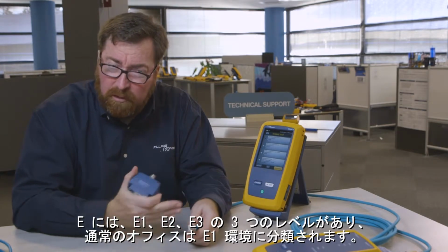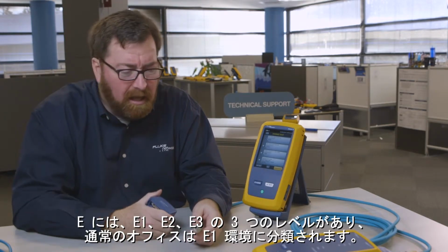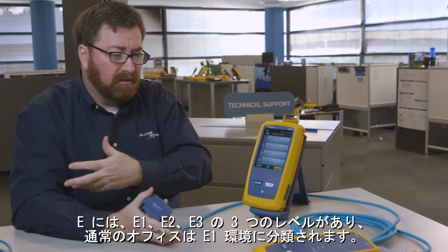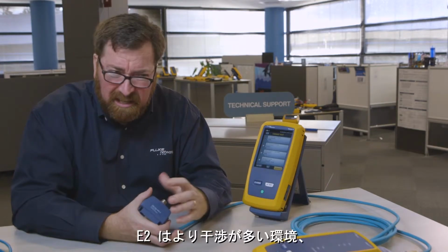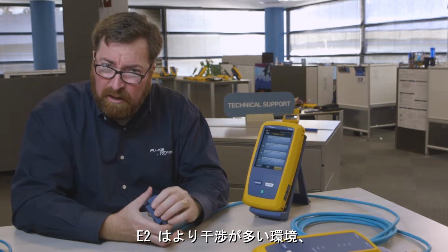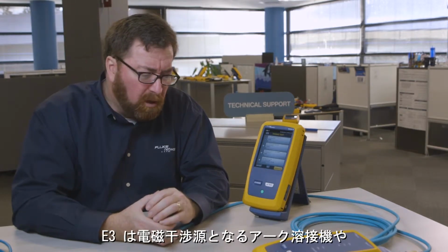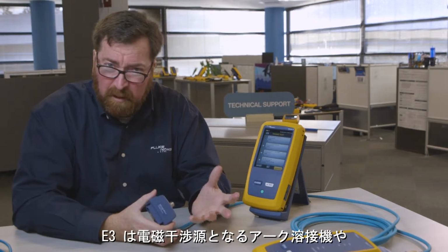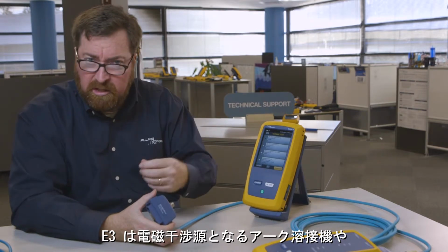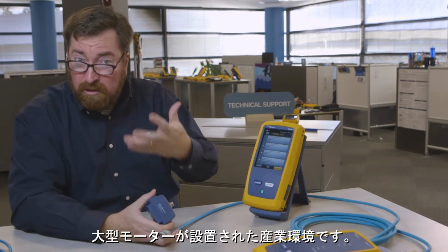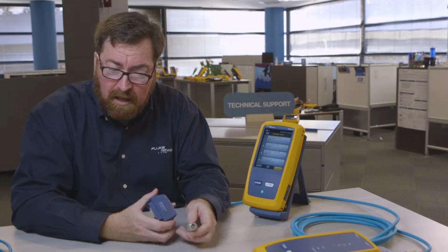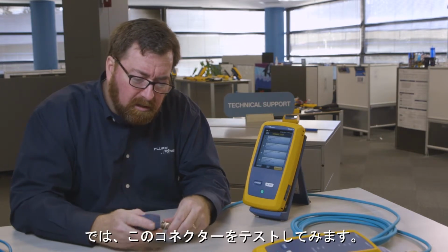There are 3 levels, E1, E2, E3. Representing a standard office would be an E1 environment. E2 would have more interference. In an E3 environment, perhaps in an industrial environment where you may have arc welding machines or large motors, are sources of electromagnetic interference. So I want to test this connector.